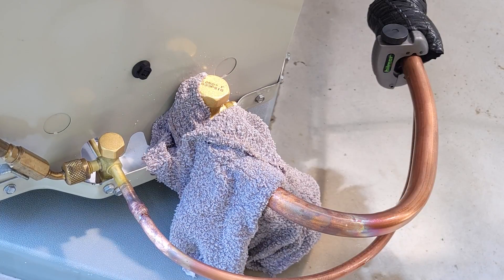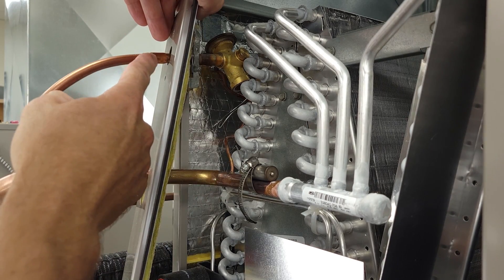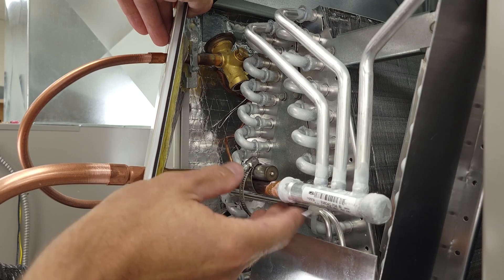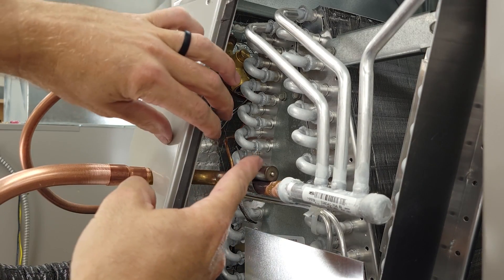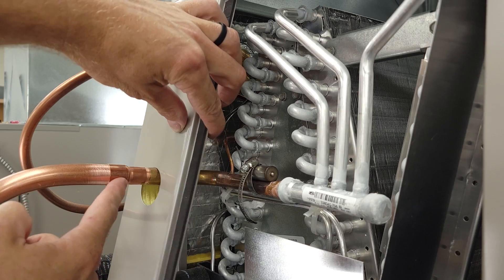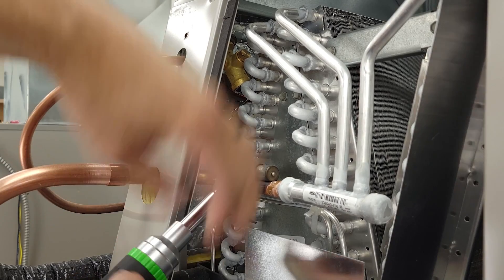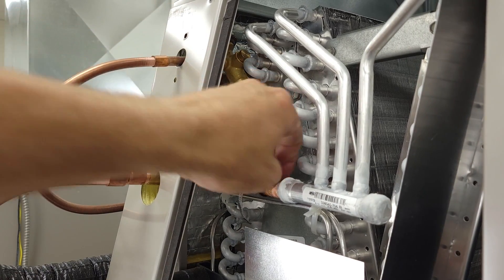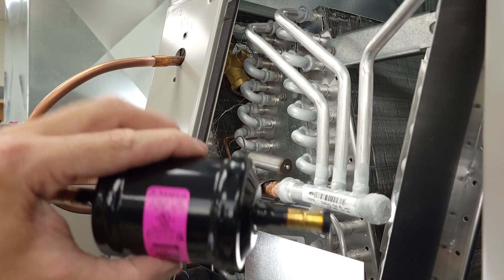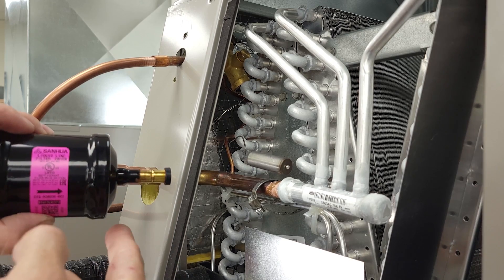Now we're going to braze the joints on the inside of the building. We're at the indoor coil and we removed both covers. You can see our thermostatic expansion valve right here, and we have one joint on our 3/8 line, so we're going to have to put a wet rag here when brazing to protect the TXV from overheating. I'm going to remove the insulation around the TXV bulb as an extra precaution because I've got three joints here — 5/8 OD going to 3/4 OD with a reducing coupling. I'm still going to put a wet rag on here because I have my copper to aluminum connection. After I braze all this in, then I'm going to braze in my filter dryer, so contaminants don't get stored in the filter dryer during the brazing process. That's why you do this last.